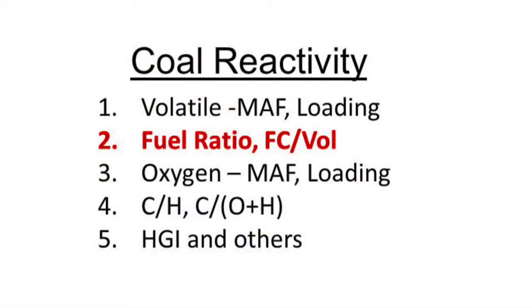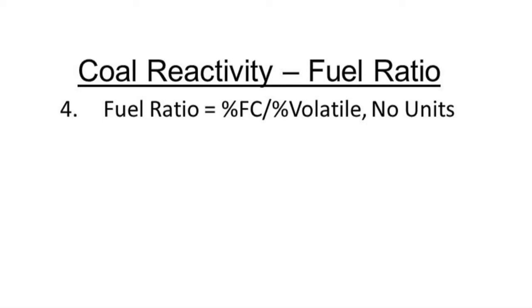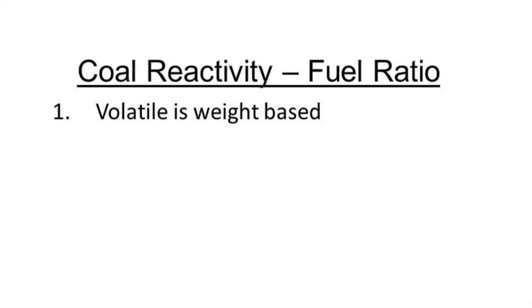One of the ways that boiler designers, boiler manufacturers, low-NOx burner manufacturers, and low-NOx people look at coal reactivity is what they call the fuel ratio, which equals the fixed carbon divided by the volatile matter. As volatile matter goes up, fixed carbon comes down, so you get a compounding impact on that. Keep in mind that the volatile matter is on a weight percent basis and the fixed carbon is also weight percent, but it's calculated by difference — so it's a somewhat inaccurate number because it carries the sum of the errors involved in the measurement of volatile, moisture, and ash.